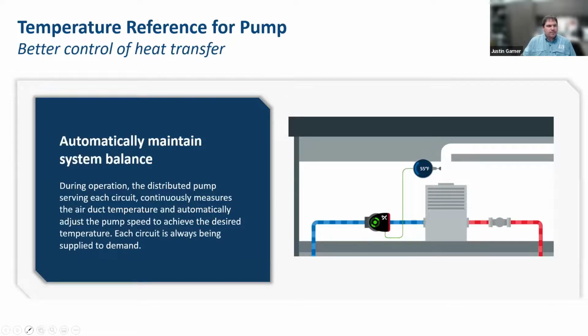From a balancing perspective, and even a building commissioning provider, or maybe even a design engineer's perspective, this is a little bit different. Obviously, we're still trying to control flow through a coil to achieve our temperature control in, say, an air handling unit. I know when PIC valves came on the market, and even some auto flow devices before that, and definitely this technology, a big question has come up. What's the role of the balancer with these types of technologies? Does manual balancing go away? Do we need water balance scope? And the answer is yes.